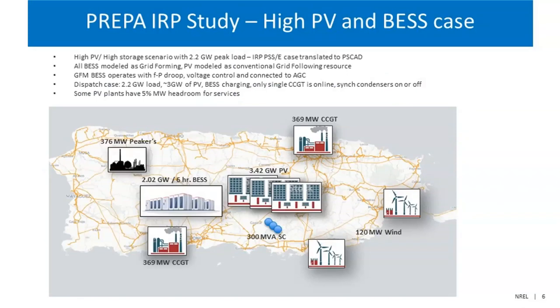This is one IRP scenario for PREPA, and you can see that the levels of variable renewable generation in the form of solar and battery storage are extremely high: 3.4 gigawatts of PV and over 2 gigawatts of storage on a system that is forecasted to have 2.2 gigawatts of peak load. So there are only very few remaining synchronous resources left, a couple of combined cycle units and also the peaker units. As part of the study, we also looked at what role synchronous condensers can play in this system in order to improve stability. So we looked at up to 300 megawatts of synchronous condensers in this system.